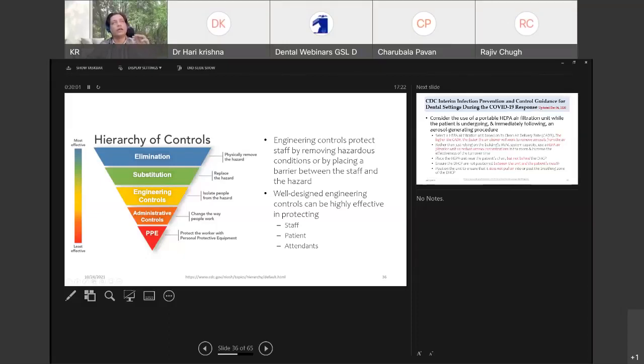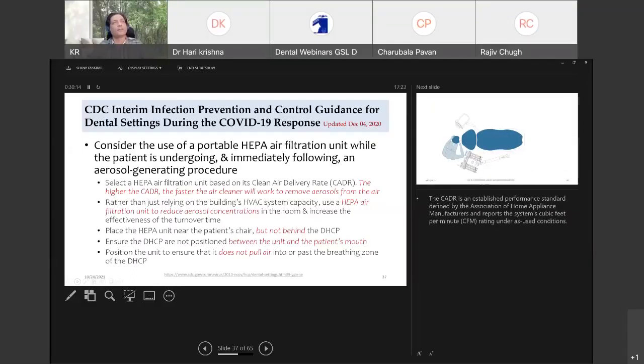Engineering controls protect the staff by removing the hazard condition or by placing a barrier between the staff and the hazard, and well-designed engineering controls can be effective for protecting the patient, staff, and attendants alike. There is a CDC Interim Infection Prevention Control Guideline for dental settings during the COVID-19 response, last updated December 4, 2020. They recommend considering the use of a portable HEPA air filtration unit while the patient is undergoing and immediately following an aerosol generating process.